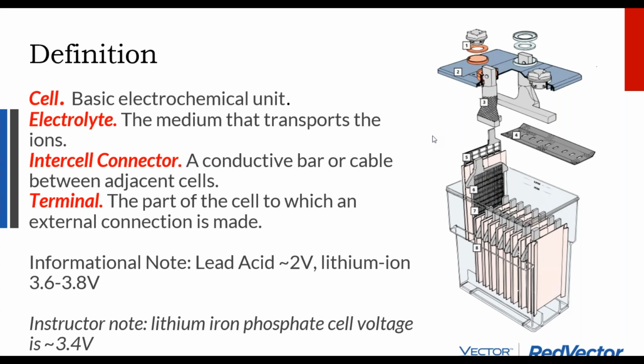Often technology will outpace the National Electric Code, and within the battery industry, just like with lead acid, there's a couple of different types of lead acid. In the lithium ion battery industry, we have primarily lithium cobalt batteries and then lithium iron phosphate batteries. Lithium cobalt has higher cell voltage, 3.6 to 3.8 volts. Lithium iron phosphate has a slightly lower cell voltage, and that results, even when you wire all these cells up to make a 48-volt battery, technology for technology, cell for cell, in a slightly lower operating voltage for the same number of cells than lithium cobalt. Lithium cobalt's like the Tesla battery. Lithium iron phosphate is almost what everyone else is using.